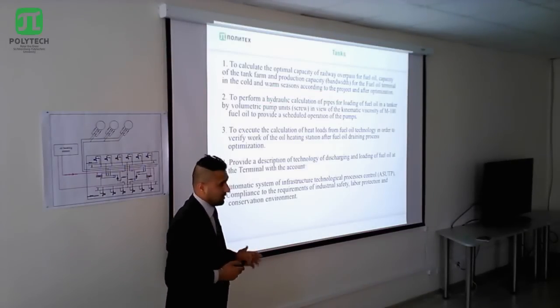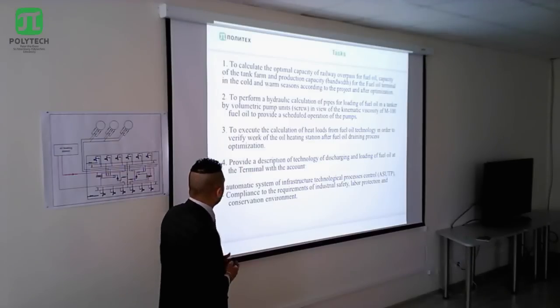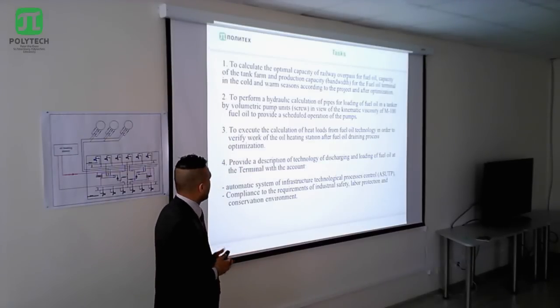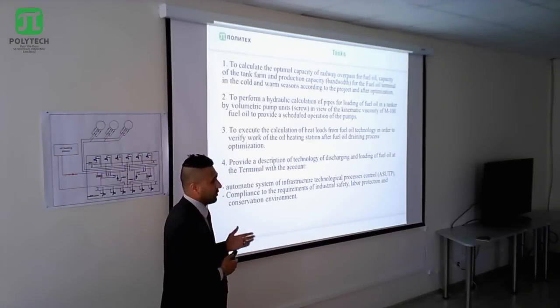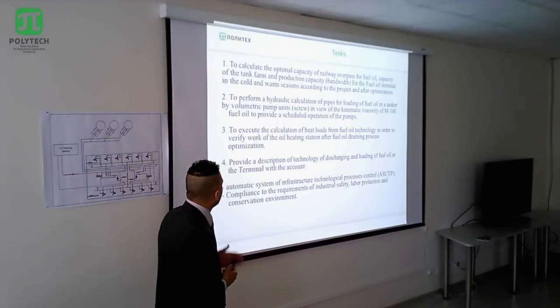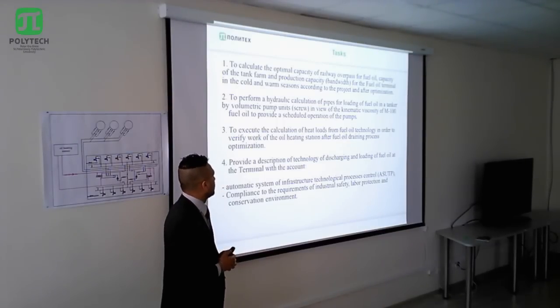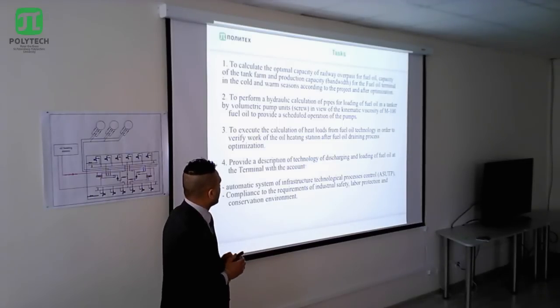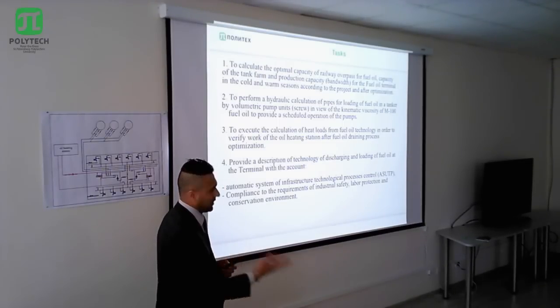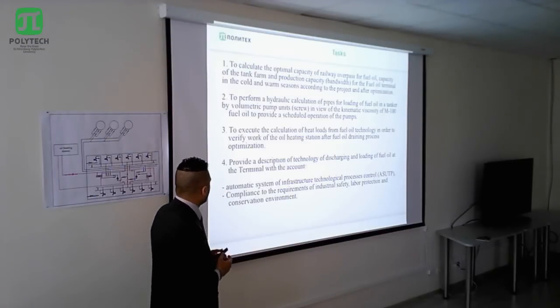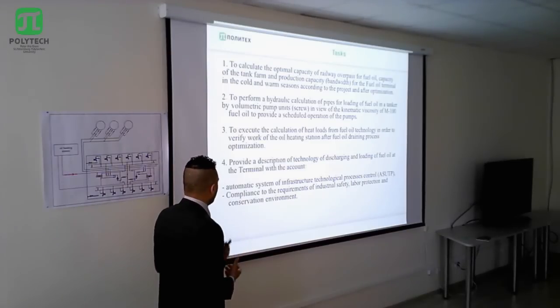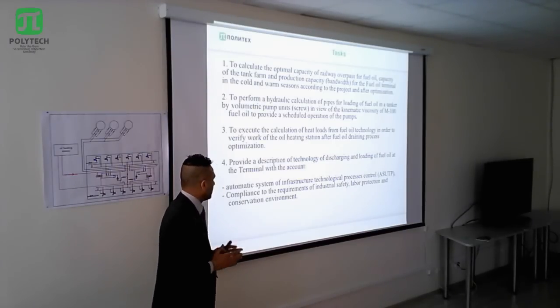I did some tasks to calculate the optimal capacity of the railway overpass for fuel oil, the capacity of the tank farm, and production capacity bandwidth for the fuel oil terminal in the cold and warm seasons, according to the project and after optimization, and also to verify the calculation of heat loads from fuel oil technology in order to check the work of the oil heating station.